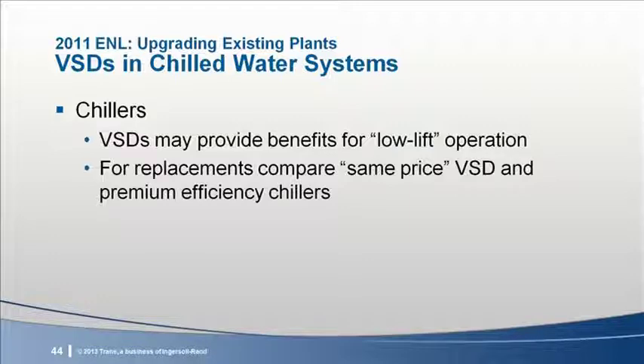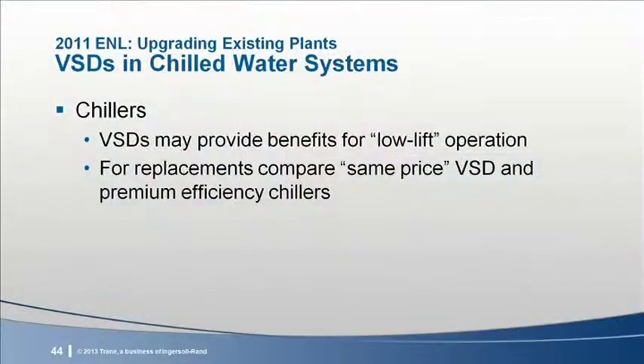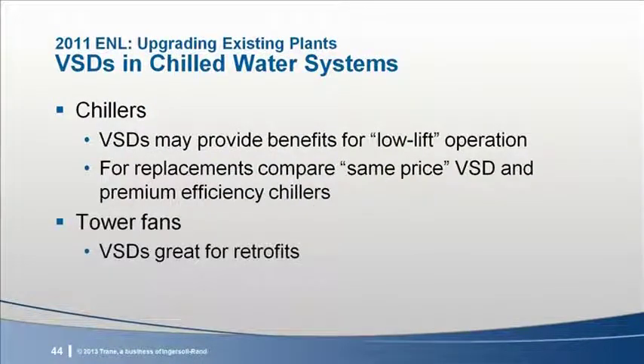If the chiller is to be replaced, compare two chillers with the same price, one with a variable speed drive and the other with more heat exchange surface and therefore premium efficiency. Perform an analysis with both demand and consumption costs. Cooling tower fans are often a great retrofit application for VFDs. From a chilled water pump standpoint, there's low-hanging fruit for applying VFDs, especially in constant flow systems.